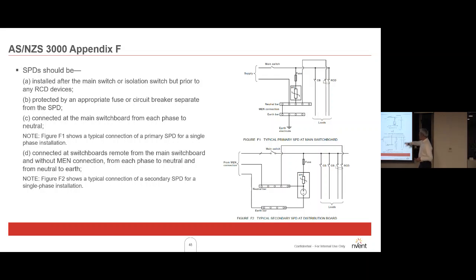And at a distribution board where you're away from the MEN link, we put in a surge protection device between there. This is showing a gas arrestor, but it could also be just a MOV like that. And quite often that's what's used in New Zealand.